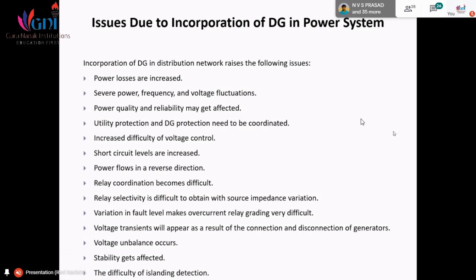But nowadays we have online grid connected systems to overcome that drawback. Online grid connected inverters are used nowadays to overcome that problem. What is the thing over there? Those online inverters generate output only when the utility is present. जब यूटिलिटी का सप्लाई होगा उसी समय आपका ऑनलाइन इन्वर्टर आउटपुट देगा. If the utility is absent, then it is not going to generate any power. Because of this, the reverse power flow problem has been resolved, and most of the accidents that happened because of reverse power flow from the DG to the utility side have been reduced.